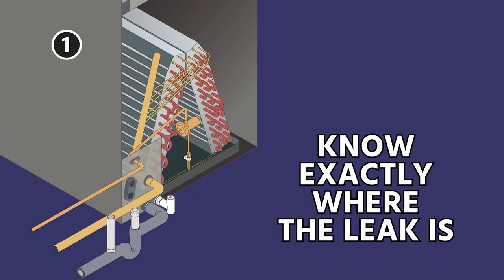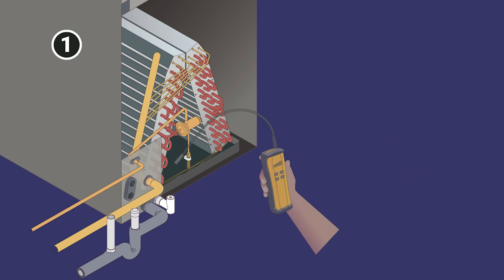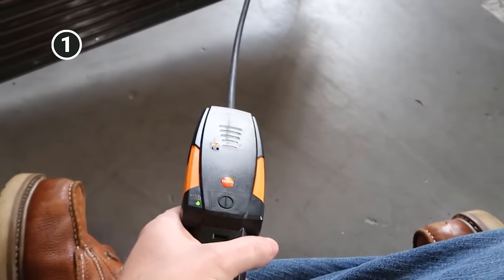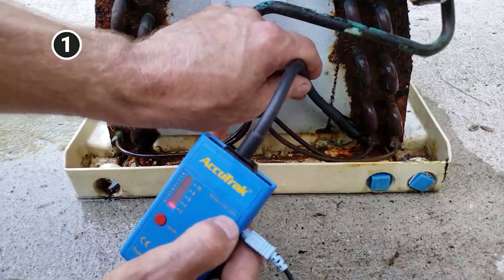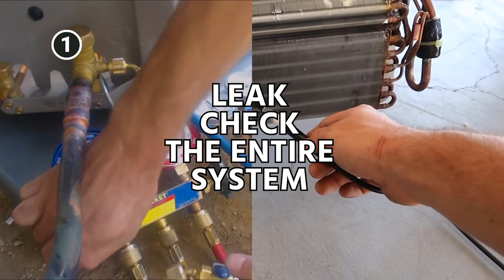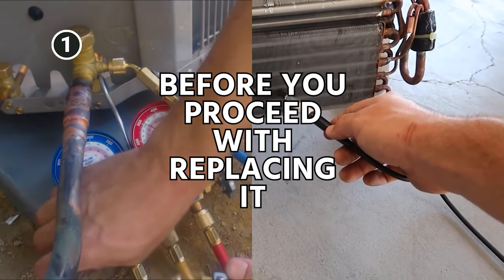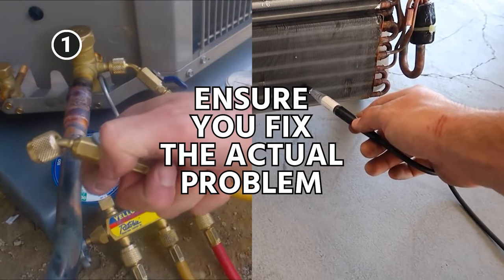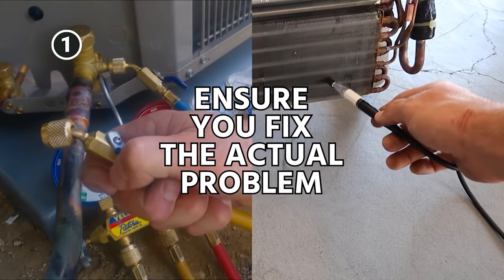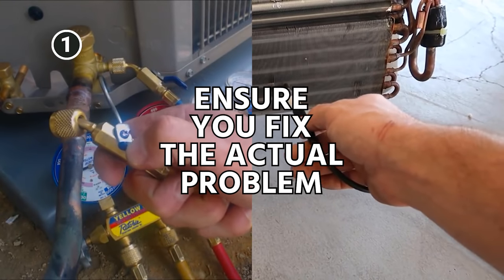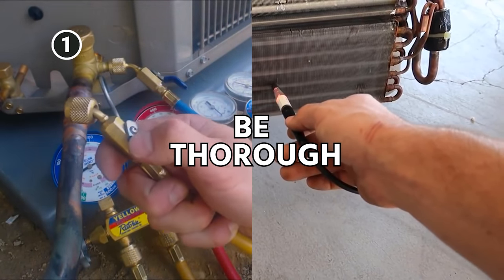So not only confirm that you know that the evaporator coil is leaking and where it's leaking with a good quality leak detector, like a heated diode electronic or maybe even an ultrasonic, but then also leak check the entire rest of the system before you proceed with replacing it to ensure that you're not going to be giving the customer a very expensive repair that won't actually fix the problem. So be very thorough in re-diagnosing.